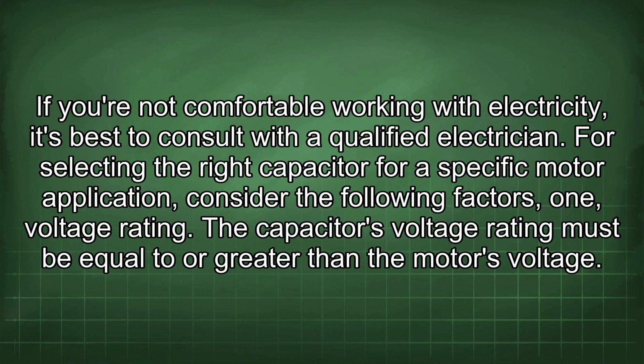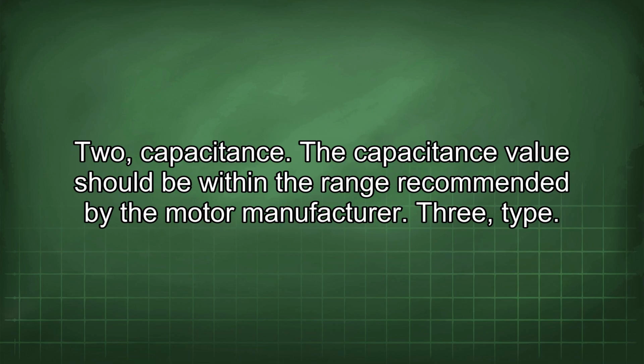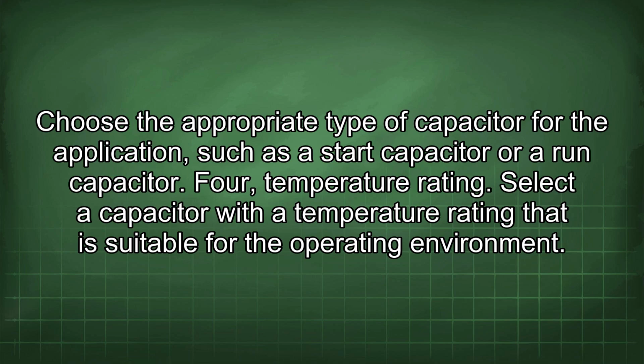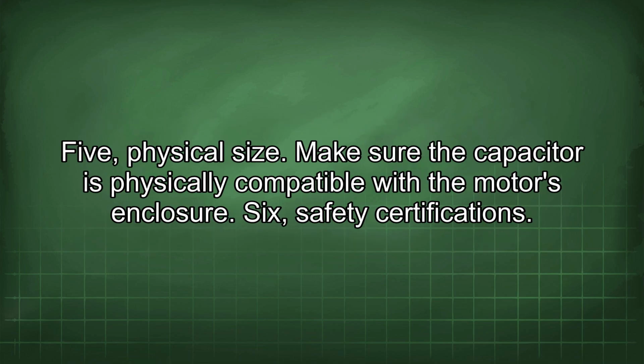For selecting the right capacitor for a specific motor application, consider the following factors. 1. Voltage rating. The capacitor's voltage rating must be equal to or greater than the motor's voltage. 2. Capacitance. The capacitance value should be within the range recommended by the motor manufacturer. 3. Type. Choose the appropriate type of capacitor for the application, such as a start capacitor or a run capacitor. 4. Temperature rating. Select a capacitor with a temperature rating that is suitable for the operating environment. 5. Physical size.